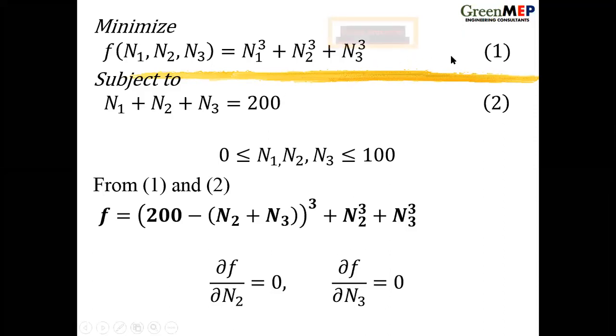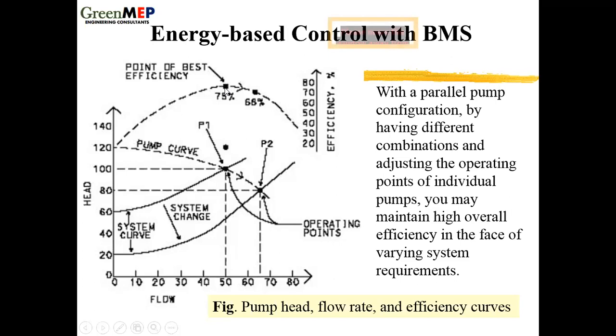Okay, so it's a multi-dimensional optimization problem, and the software uses well-known techniques that are applied here. But you have to go further. Just adjusting the speed is not sufficient, because if you look at, for example, the pump efficiency curve, unfortunately, it has this kind of scenario. This is the pressure or the head of the pump. This is the flow, right? It's not flat. Because it's not flat, you can see if you stay here, the efficiency is 75%. That means 25% of the electric energy input is wasted. Anyway, wasted. Can't help.